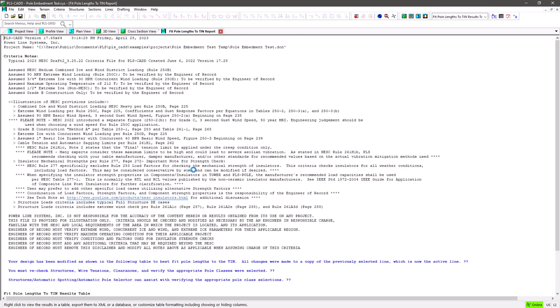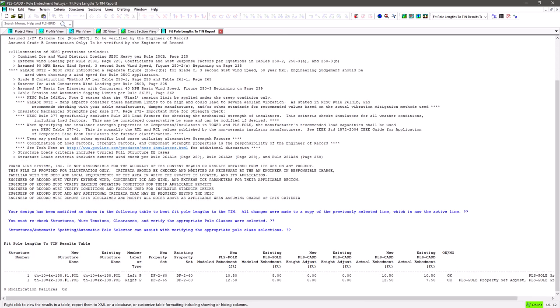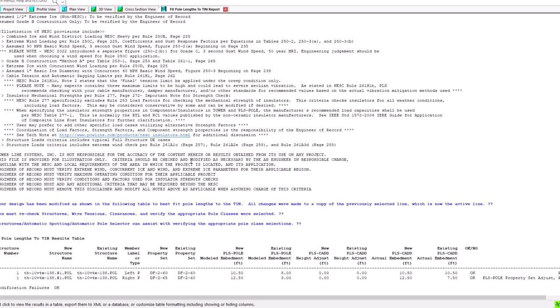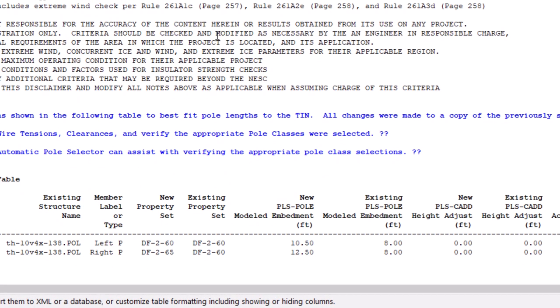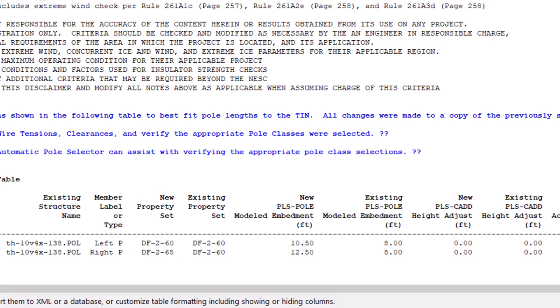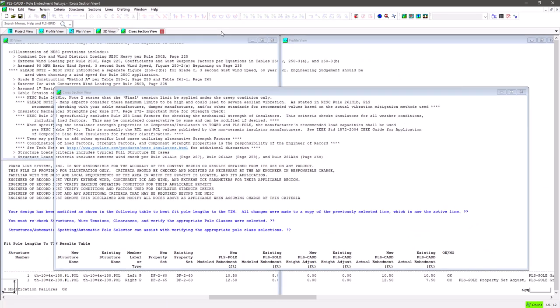Here you can see the results showing both poles had an existing embedment of 8 feet, but now the left pole shows an embedment of 10.5 feet, and the right pole, since it was above the tin and we specified no under embedment allowed, it had to put in a 5 foot taller pole and then over embed it by 4.0 feet for a total embedment of 12.5 feet.